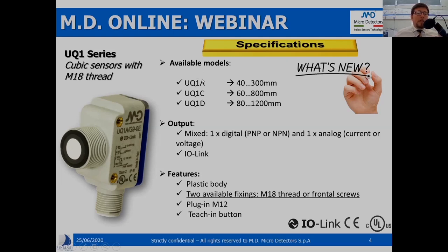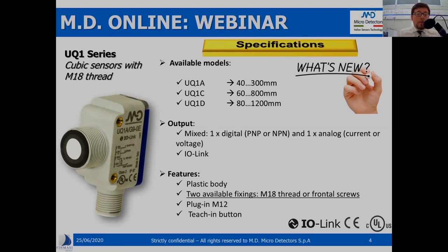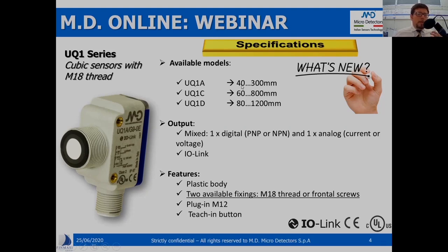A first clustering of our models can be based on the operating range. We can distinguish among three subfamilies: UQ1A, UQ1C, and UQ1D. The first has a distance from 40 to 300 mm; the second from 60 to 800 mm; and the last from 80 to 1200 mm. The minimum distance is the so-called blind zone or dead zone — within this minimum distance, the models are not able to detect echoes coming back from target surfaces.